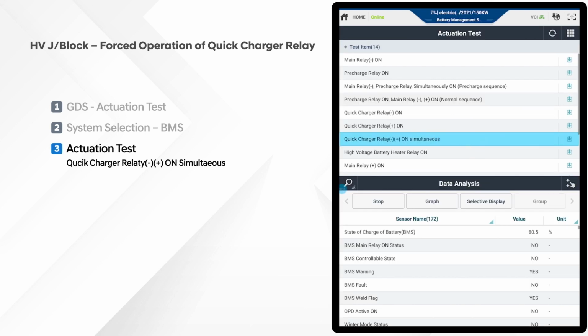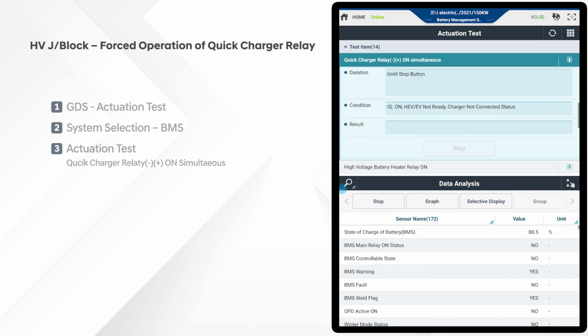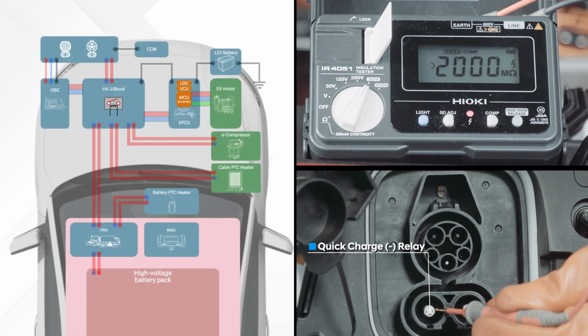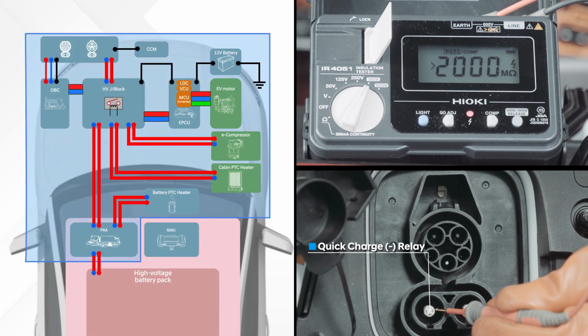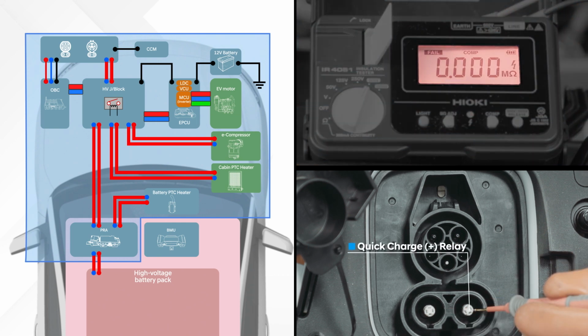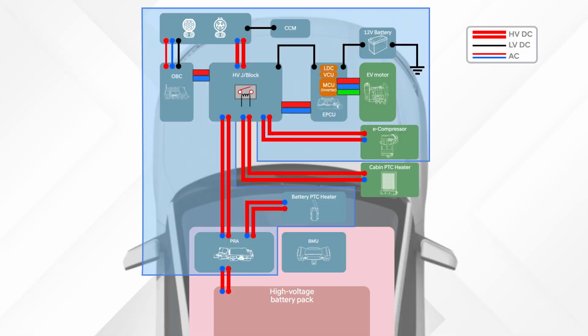Now, after turning on the quick charge relays of the high voltage junction block, check the condition between the charging inlet DC terminal and the vehicle body. The insulation resistance of the charging inlet DC minus terminal is open loop. It is normal. The insulation resistance of the charging inlet DC plus terminal is abnormal. Then you should narrow down the trouble area.